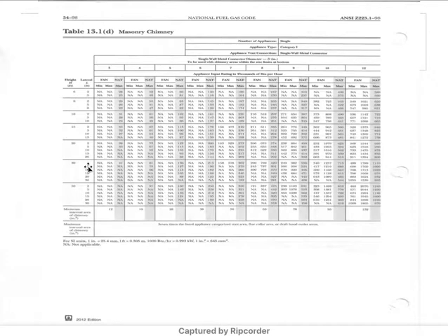And then, as I said at the beginning, you have fan, minimum and max. That's your fan assisted. You don't want that. We're working with a natural vent appliance here. So we're going to be in this column. So we have rounded up to 30, we're at 5, and 40,000 BTUs. First column, we have anything, 75, that's fine. 4-inch.